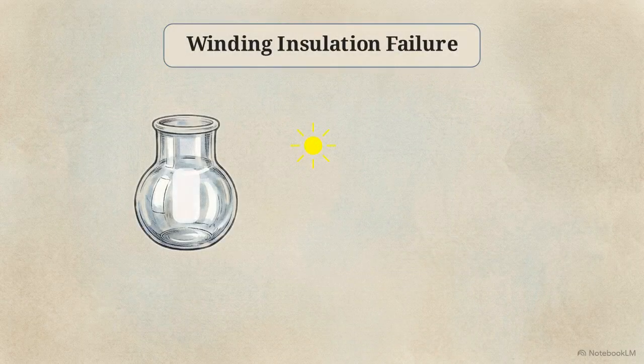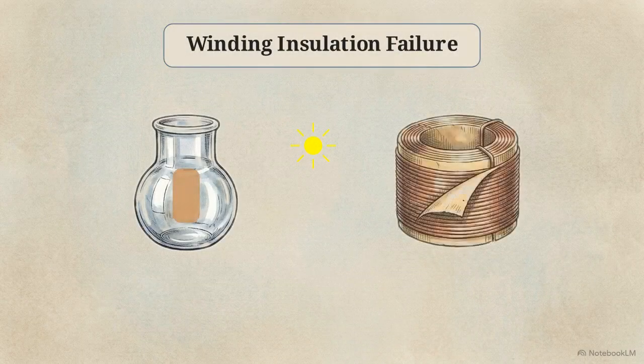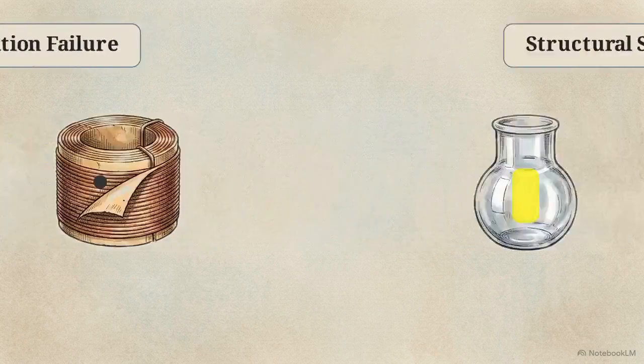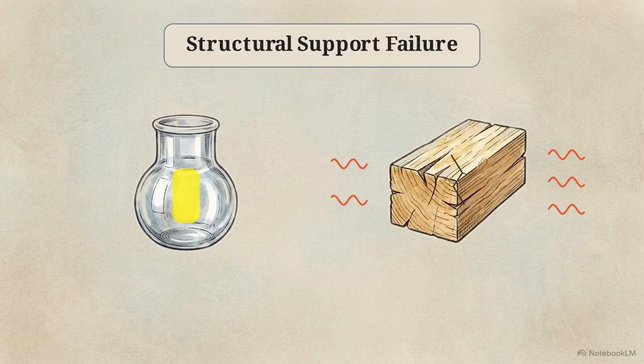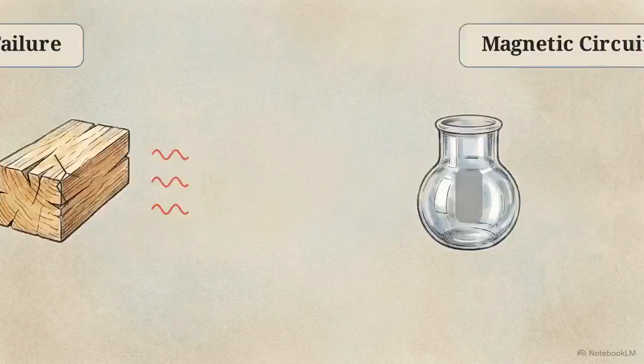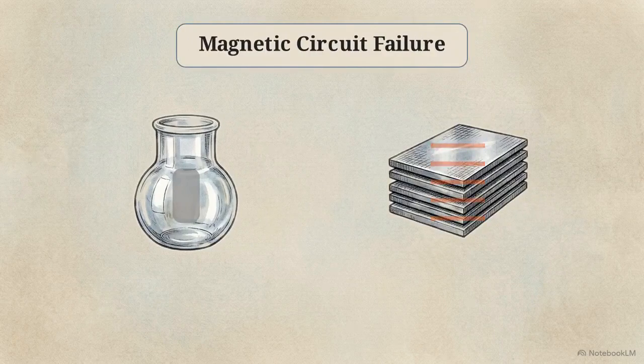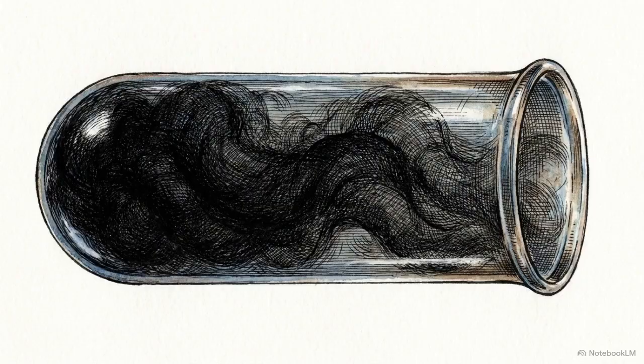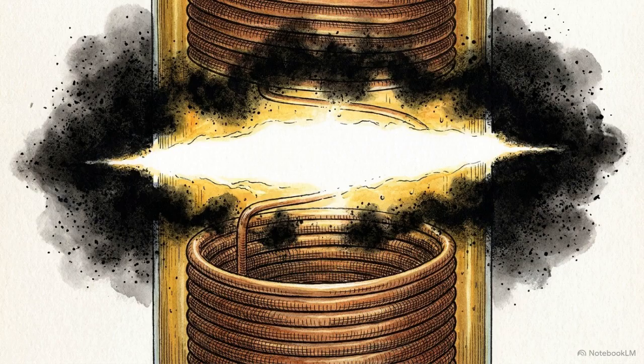If the analysis reveals a white gas that slowly turns brown under light exposure, it indicates that electrical arcing occurred directly against the paper or cotton insulation wrapped around the windings. A yellow gas points to the degradation of structural wood or cardboard supports. A grayish gas proves a breakdown occurred within the magnetic core laminations. The most severe diagnostic finding is a black gas. This confirms that free electrical arcing erupted directly within the insulating oil itself, signaling massive internal destruction.